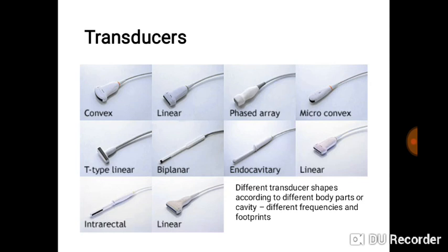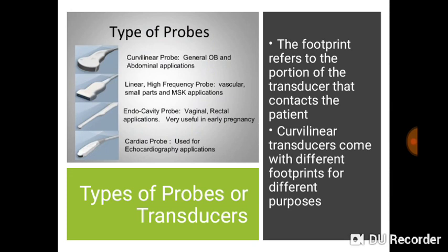There is a range of probes you will encounter in practice. You have the convex/curvilinear, the phased array — more like the linear and convex but with a smaller footprint and smaller surface area — and the microconvex, similar. You also have endocavitary probes for transvaginal, transrectal, and transesophageal use. The footprint of a probe refers to the surface area that makes contact with the patient. Curvilinear transducers come with different footprints for different purposes.